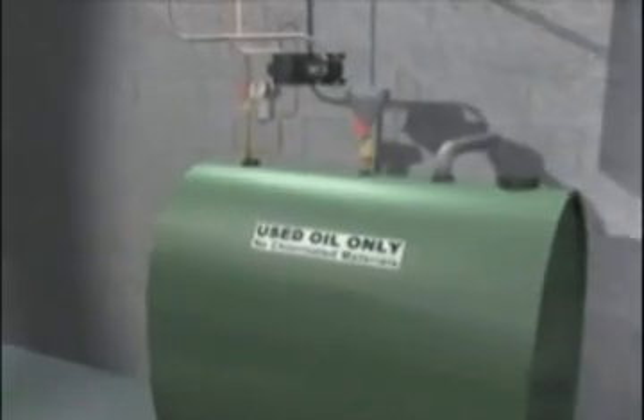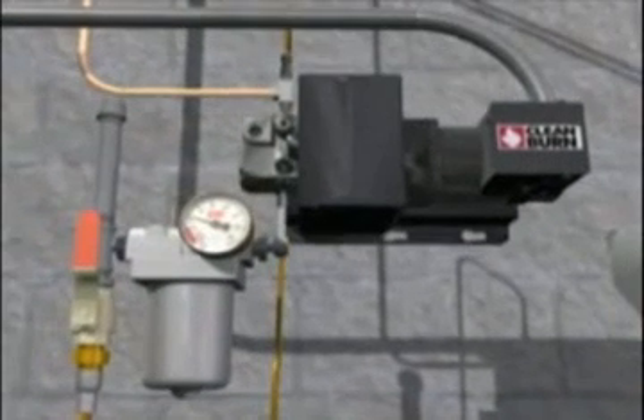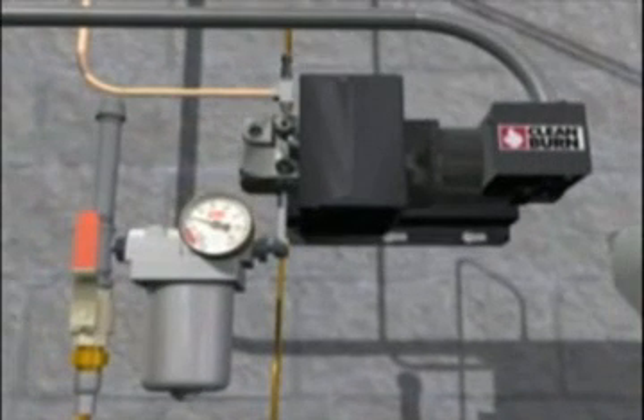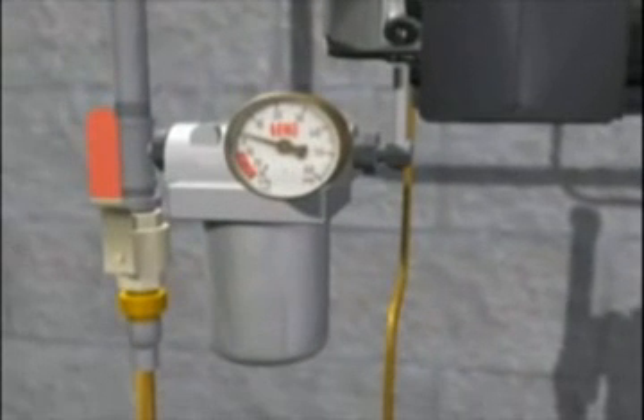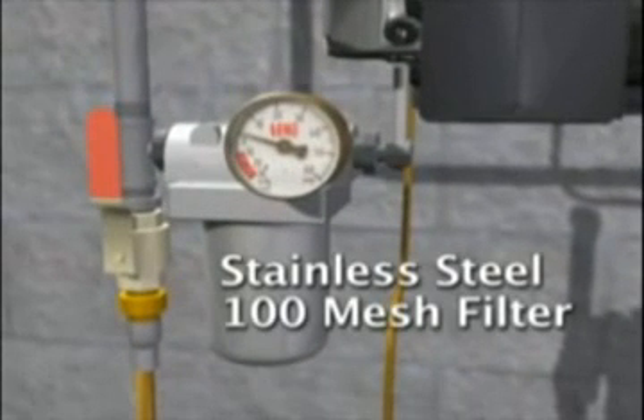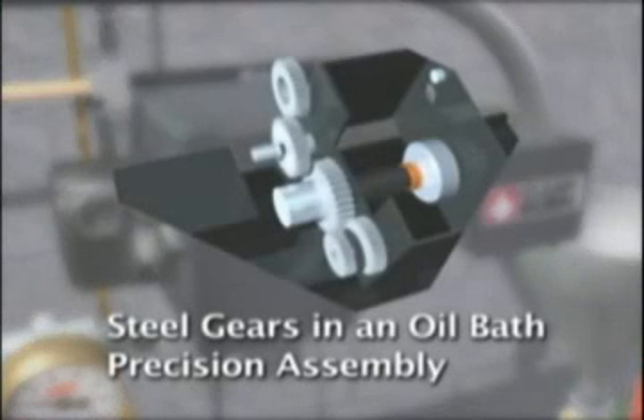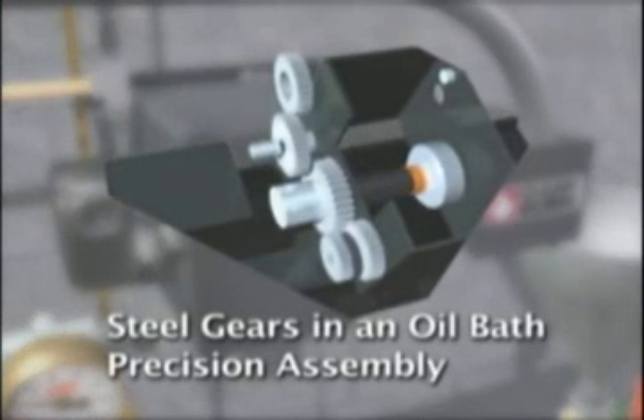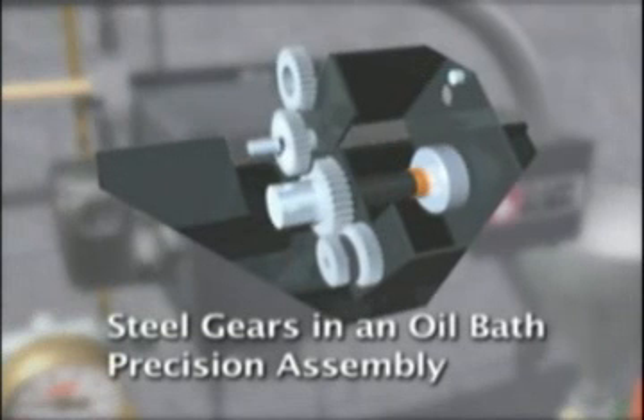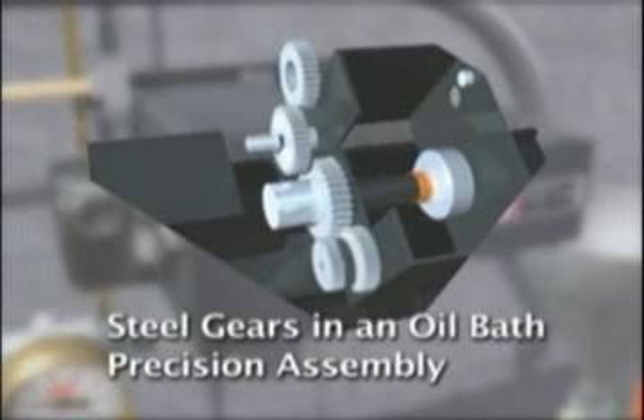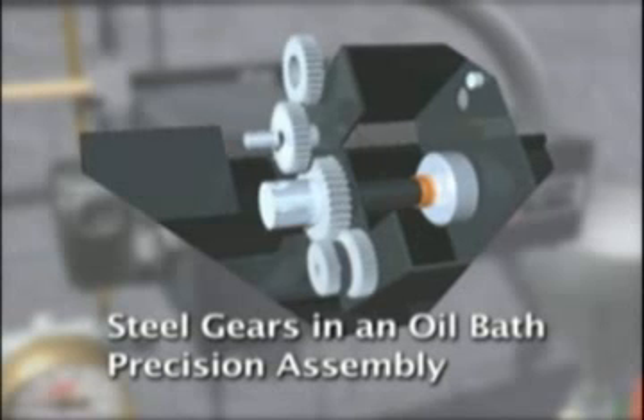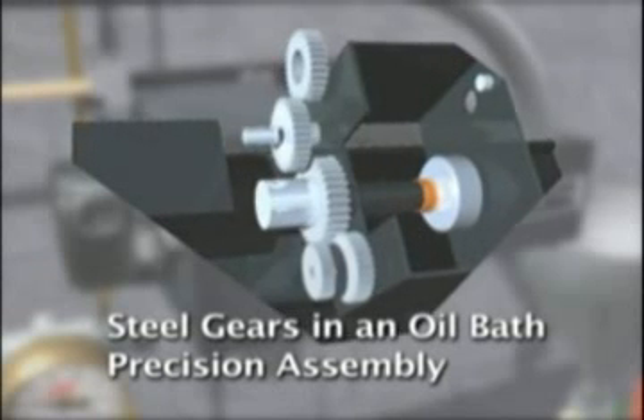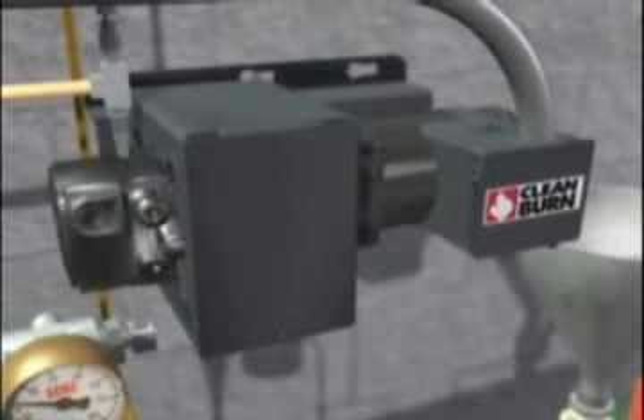The oil pump assembly receives electrical power and is switched by the furnace burner. Oil is drawn from the storage tank and through the filter, removing gross impurities. Its stainless steel 100 mesh filter is washable in a parts washer. The fuel flow control pump features heavy-duty steel gears encased in an oil bath and a precision assembly to help ensure a long, reliable service life. The oil flow rate is consistent due to precise gear ratios and pump speeds set for each individual furnace. Correct flow rates are maintained, ensuring optimum performance.